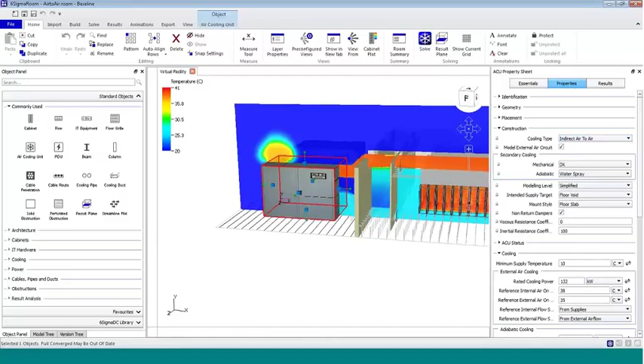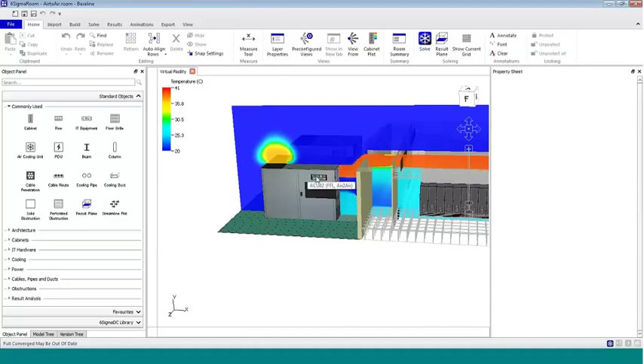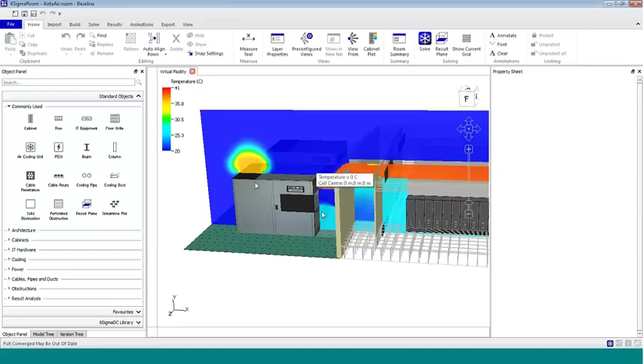This is where a lot of new technology is getting popular, with air handling units becoming much more efficient. People want to avoid spending too much on cooling to bring their PUE down. One of the neat technologies is the ability for CRAC units to exchange air and transfer heat out of the room via the external environment.